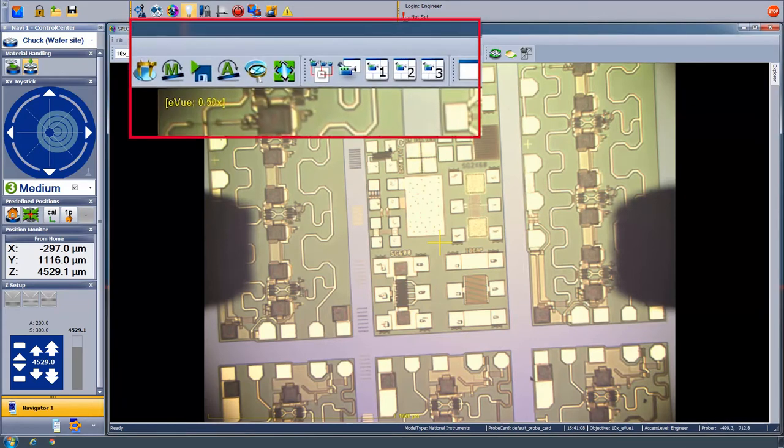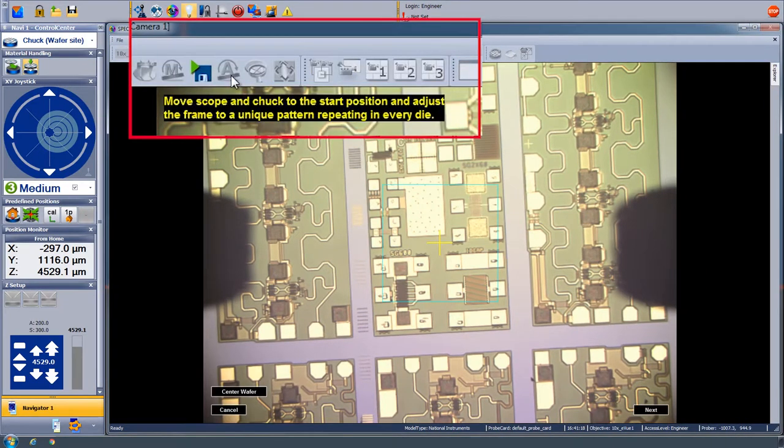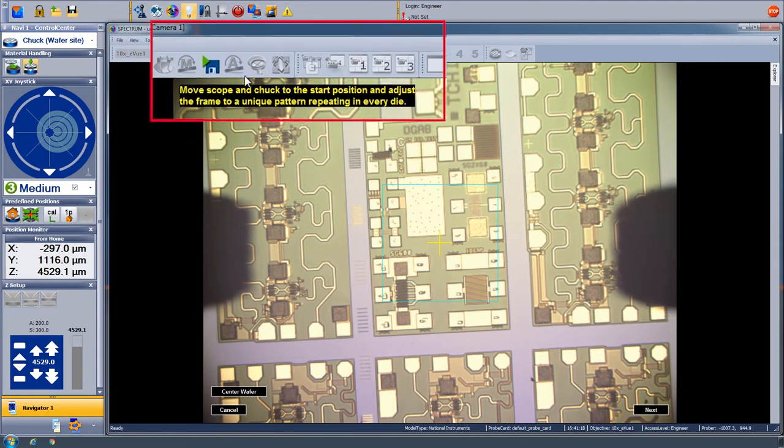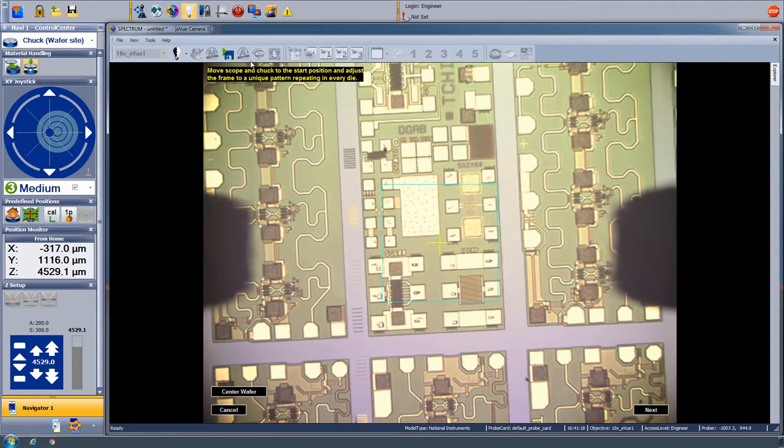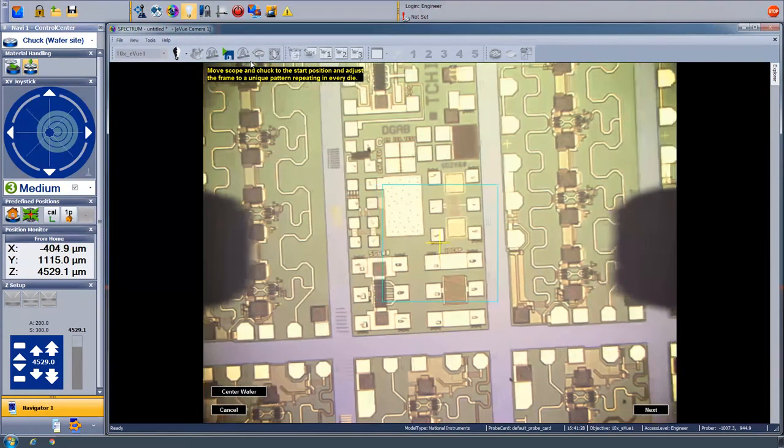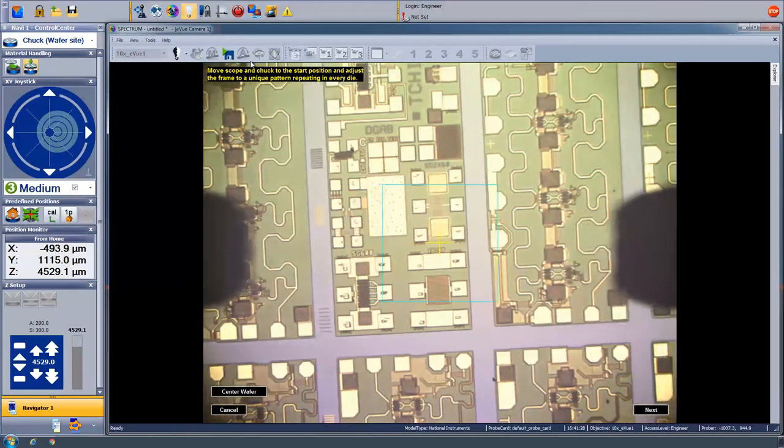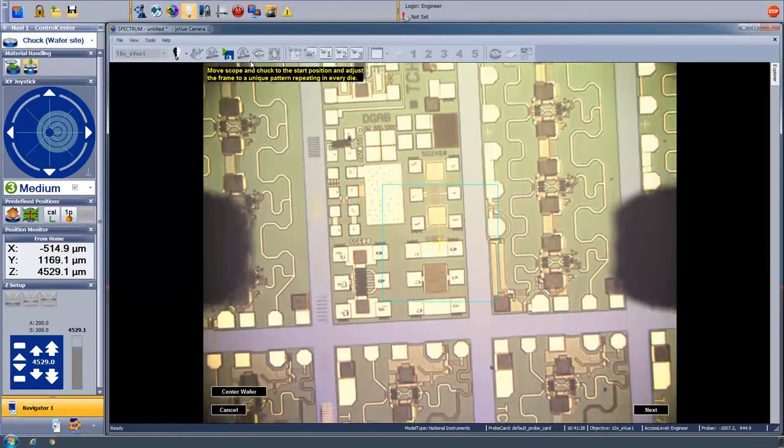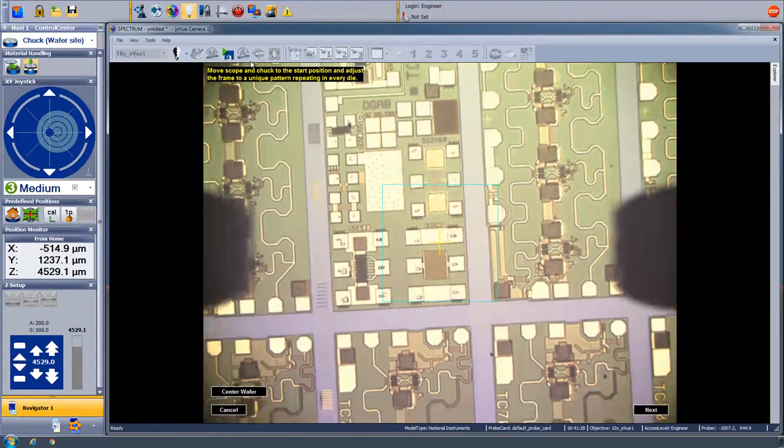Once we click the button with the A on it, it instructs us to move the scope and chuck to the start position where there is a unique pattern that repeats across the die. Using the joystick at the side of the prober, we've chosen a large capacitor structure with its associated pads.